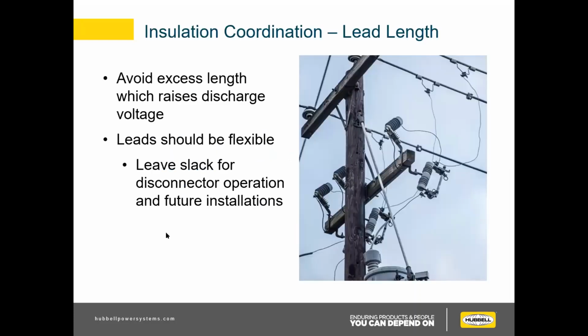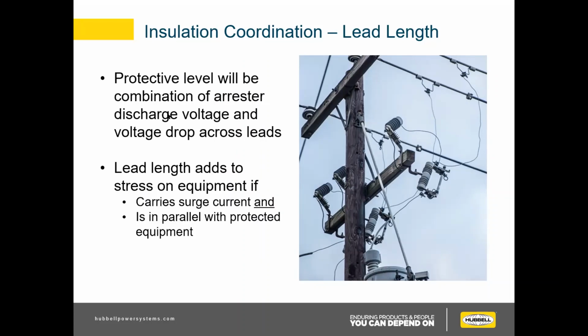So at a high level, if you don't remember anything else, remember to avoid excess lead length, because this can raise the discharge voltage of your arrestor. Your leads should be flexible so that you have a visual indication if the arrestor operates, and so you can install future installations without too much trouble. Like I said, the protective level will be the combination of the arrestor discharge voltage from a sales drawing or catalog, in addition to the voltage drop across your line leads.